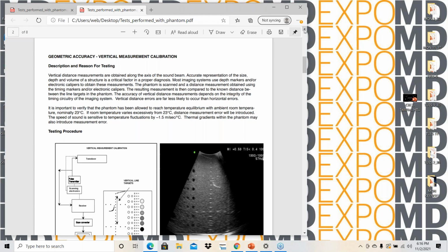And then you need to do the same measurement. Are they blurring together or not? Can you distinguish if they're two separate objects? This little curved array here is called the resolution array, because that's an opportunity for you to use the phantom and see if you have both axial and lateral resolution. Okay, it'll be a curved array, and it's not just the ATS that does that, it's in the phantom. They'll give you an opportunity to see axial and lateral.